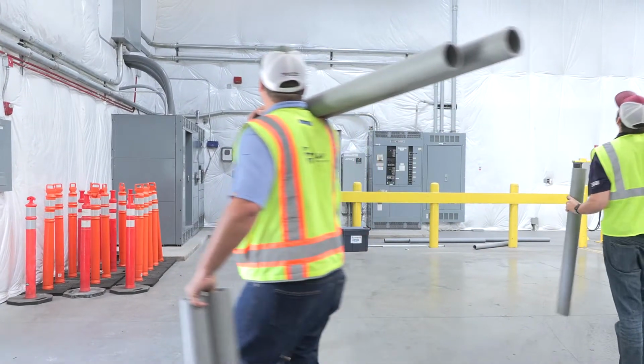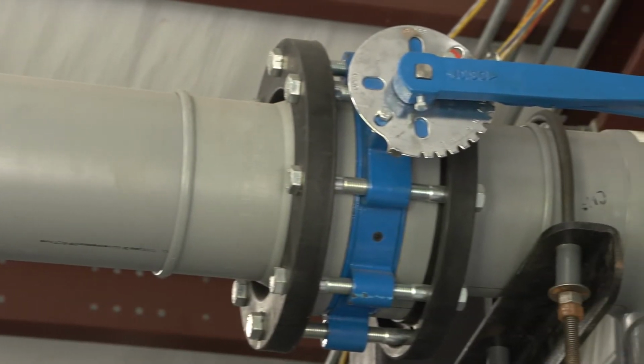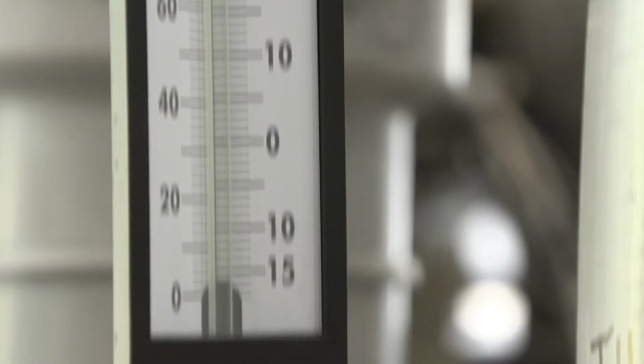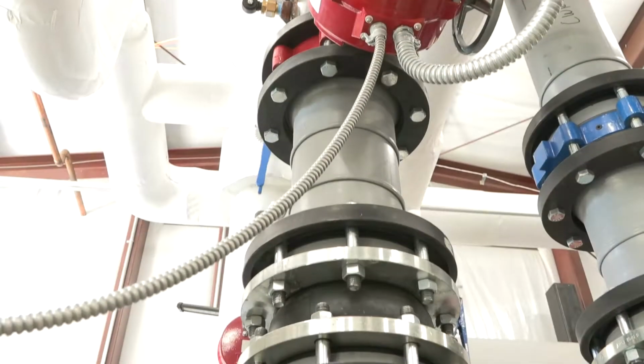You were used to welding carbon steel pipe or threading, and the time it takes to do that. We were able to roll up, face a piece of NIRON, put it in the fusion machine, and once the cool down time was done, we were on to the next one. We weren't leaving a big footprint of having to spread fire blanket and worrying about being in a working distribution center. That would have been a big deal, to have fire protection shut down, welding blinds up, things like that. With the NIRON, we just had a little bit of shavings at the end and clean that up and move on to the next weld. No shutdowns to the facility for anything with our installation.